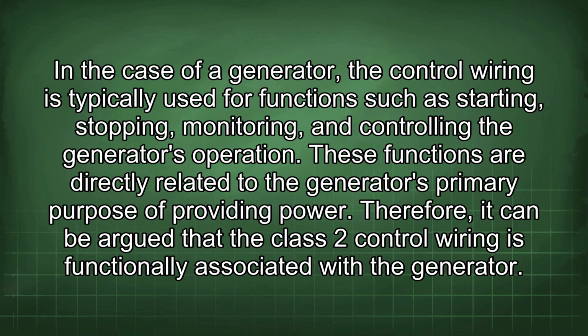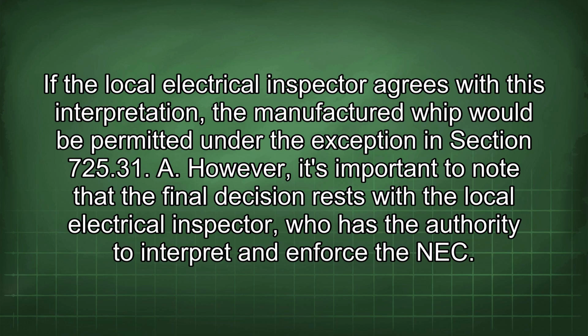In the case of a generator, the control wiring is typically used for functions such as starting, stopping, monitoring, and controlling the generator's operation. These functions are directly related to the generator's primary purpose of providing power. Therefore, it can be argued that the Class 2 control wiring is functionally associated with the generator. If the local electrical inspector agrees with this interpretation, the manufactured whip would be permitted under the exception in Section 725.31. However, it's important to note that the final decision rests with the local electrical inspector, who has the authority to interpret and enforce the NEC.